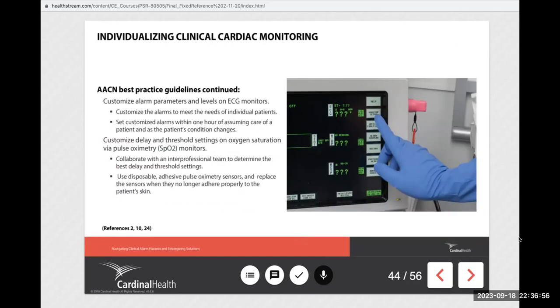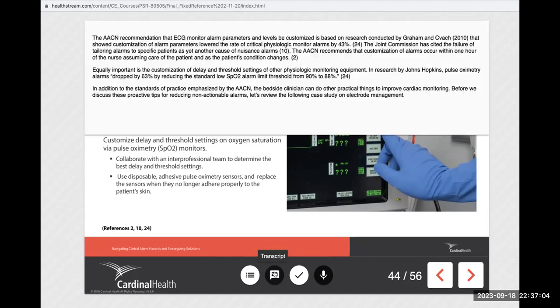The AACN recommendation that ECG monitor alarm parameters and levels be customized is based on research conducted by Graham and Kvach that showed customization of alarm parameters lowered the rate of critical physiologic monitor alarms by 43%. The Joint Commission has cited the failure of tailoring alarms to specific patients as yet another cause of nuisance alarms. The AACN recommends that customization of alarms occur within 1 hour of the nurse assuming care of the patient and as the patient's condition changes. Equally important is the customization of delay and threshold settings of other physiologic monitoring equipment. In research by Johns Hopkins, pulse oximetry alarms dropped by 63% by reducing the standard low SpO2 alarm limit threshold from 90% to 88%.